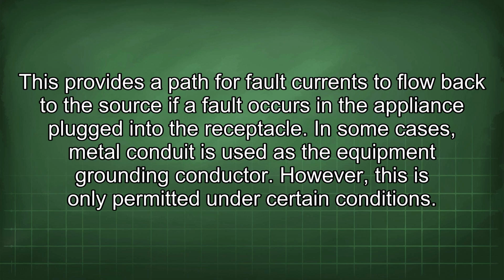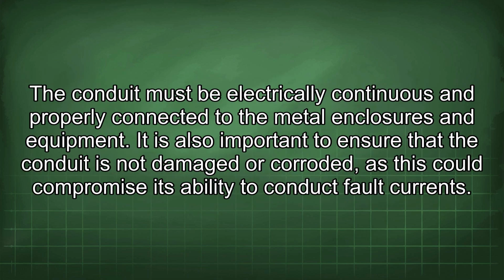plugged into the receptacle. In some cases, metal conduit is used as the equipment grounding conductor. However, this is only permitted under certain conditions. The conduit must be electrically continuous and properly connected to the metal enclosures and equipment.